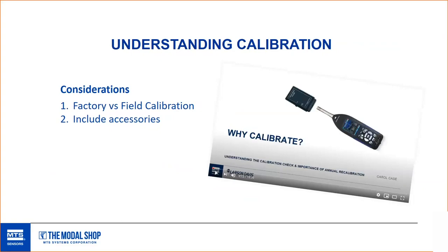The field calibrator can be calibrated by the factory and get quite a bit of data, but that doesn't mean field calibration isn't important. Like we mentioned before, the ambient pressure is an important part of how your system can slightly vary from your air-conditioned, nicely tempered lab. So do that field calibration - we actually made a whole webinar on this topic that we'll include in the links we send later.